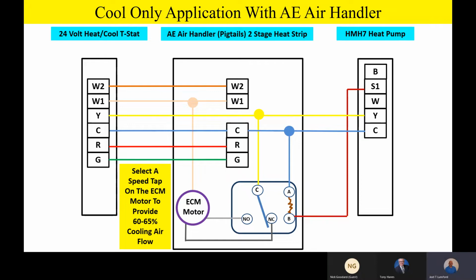And so we're going to always recommend that you have that S1 airflow reduction because that really gives you a wonderful level of comfort and all that. But if you're absolutely stuck with 2 wires and there's nothing you can do about it, then go ahead and reduce your airflow on the indoor fan to about 350 if you're in a humid environment. Otherwise, if it's not an issue, keep it at 100% cooling airflow at 400 CFM per ton. Excellent question. Any other good questions or comments?